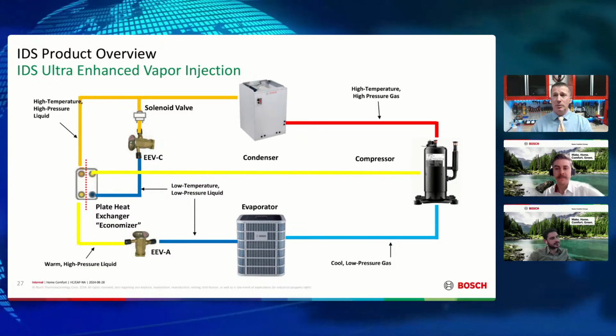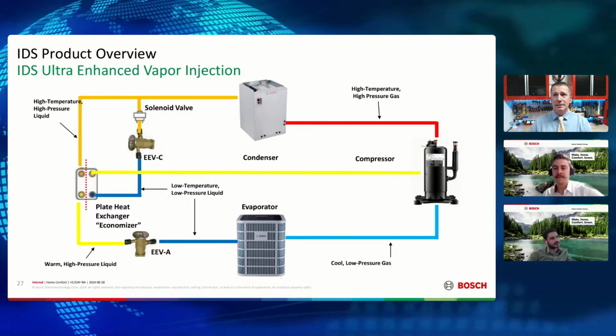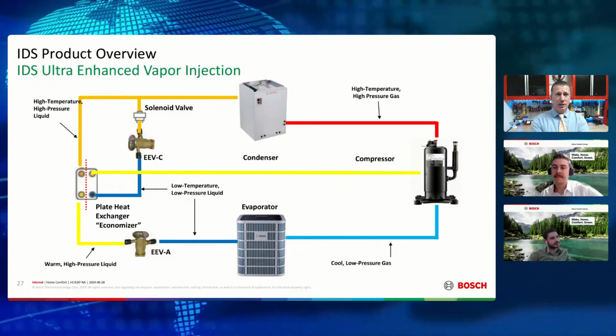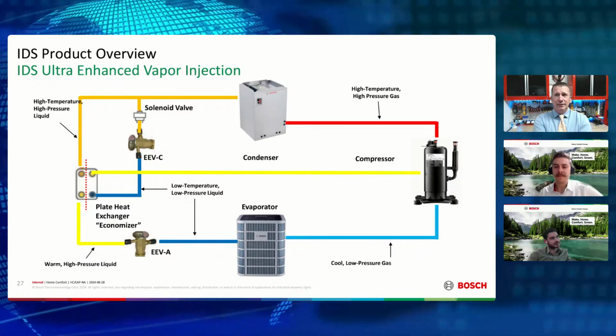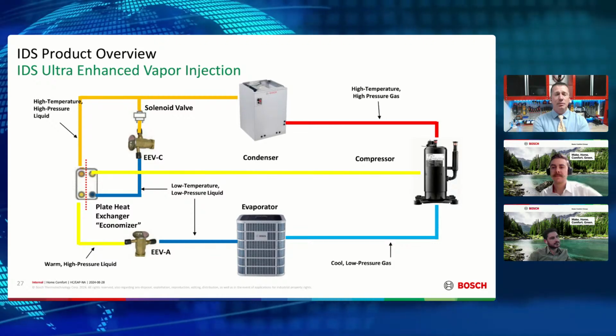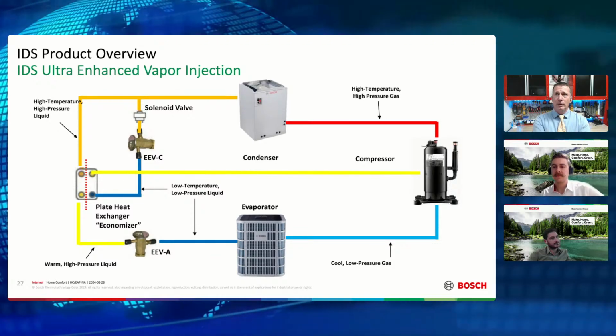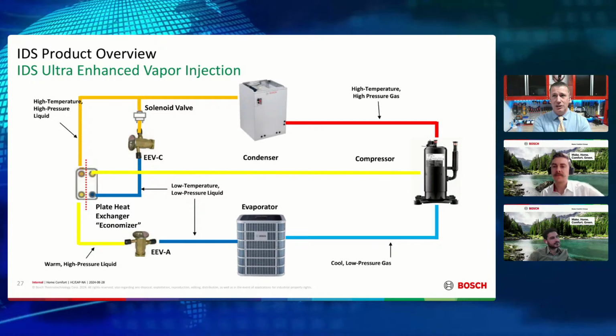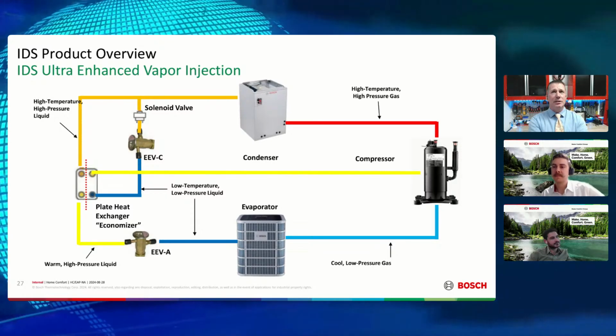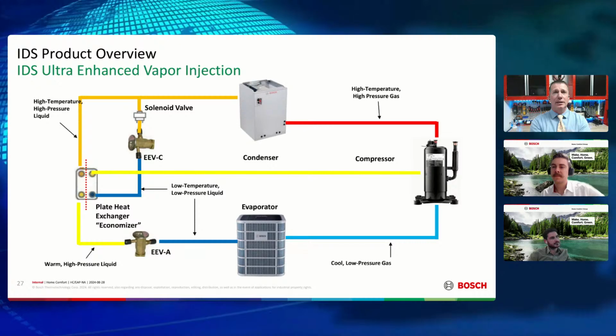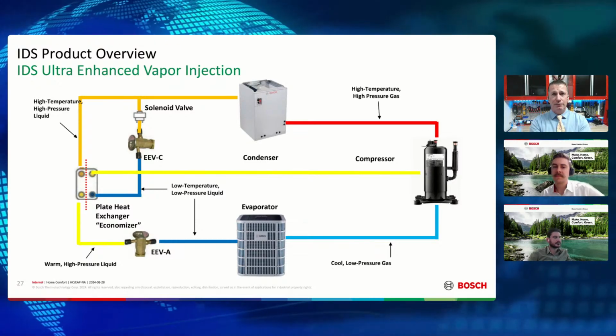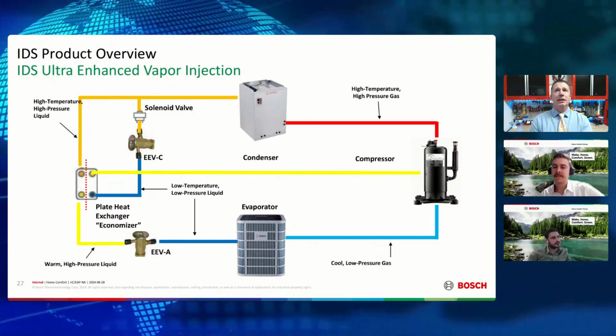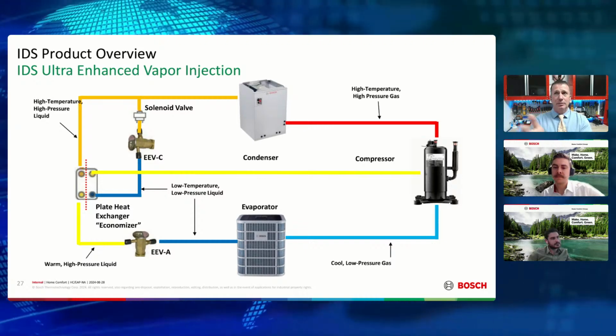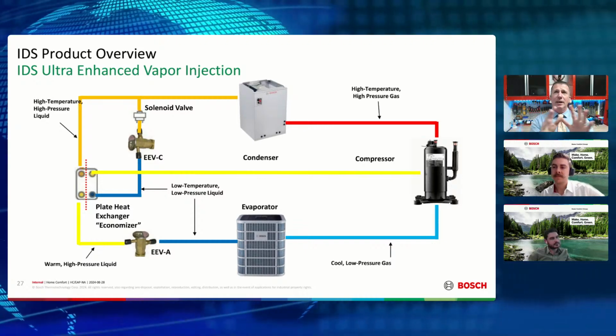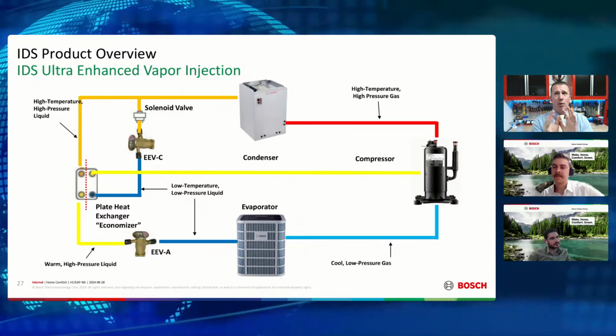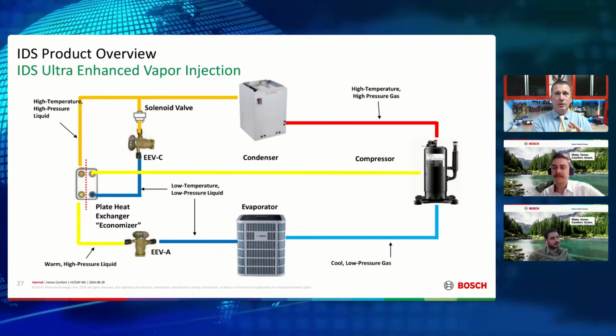When you think about the principle of it, it just makes sense. The reason I brought up the evaporator target temperature is that, particularly in the South, we have complaints from contractors who struggle with inverters and dehumidification. I think it's because they're not as well educated on the function of variable speed blowers and their effect on capacity with an inverter. I know we're talking about heat pumps, but I want to shed light on the importance of this technology in cooling mode as well.